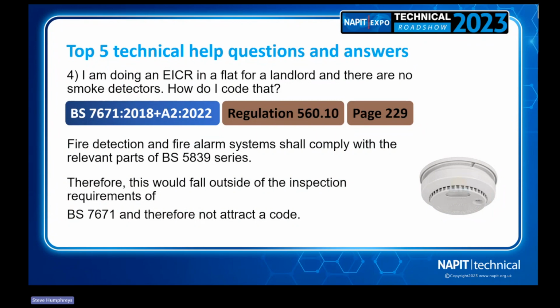It's also worth noting, if this question said there are existing smoke detectors, although the detectors themselves wouldn't fall under BS 7671, they'd fall under BS 5839. As said, the hard wiring or the supply to them, if they're mains wired, would fall under the scope of BS 7671 and any EICR that you were performing. For example, if the inspector finds the cables not supported and subject to collapse, and could cause entanglement, for instance, then we're going to give that a C2 because it's an endangerment to life. So the wiring, yes. The actual equipment in this instance is a no.